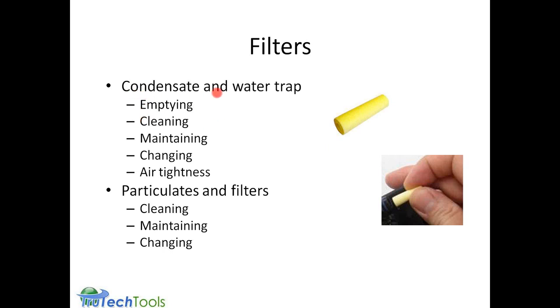When you do empty the condensate and or the water trap or the particulate filters, you have to remember about the air tightness issue. Make sure everything's sealed back up again. Otherwise, you let ambient air into the system, and then that causes an issue with the air gas measurements.